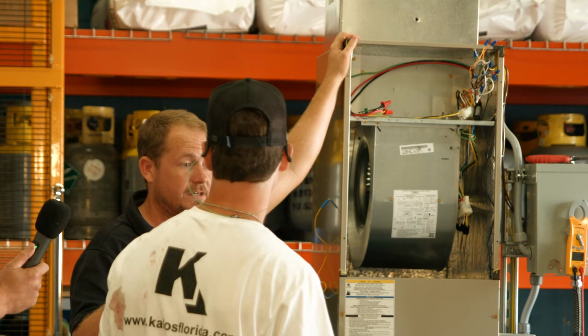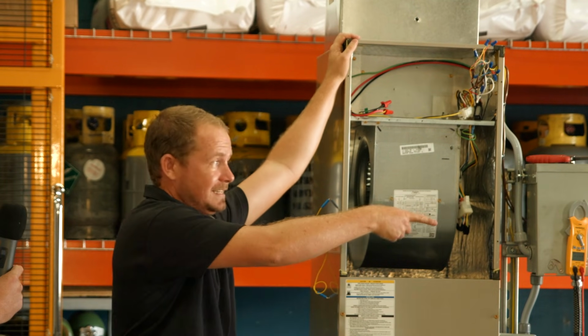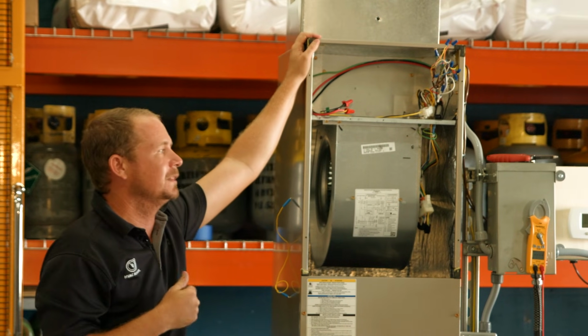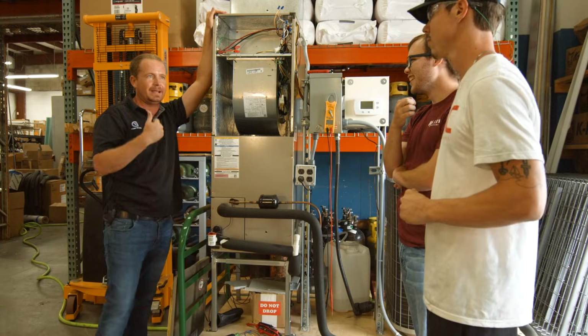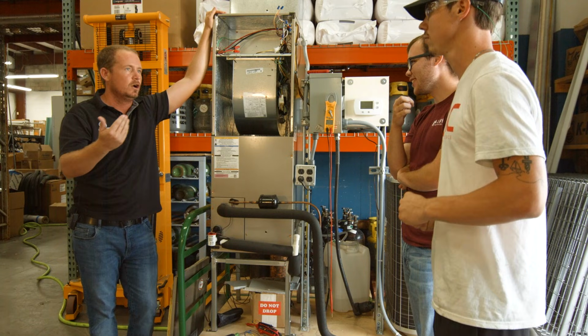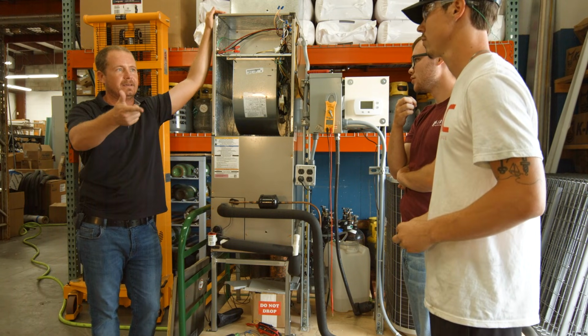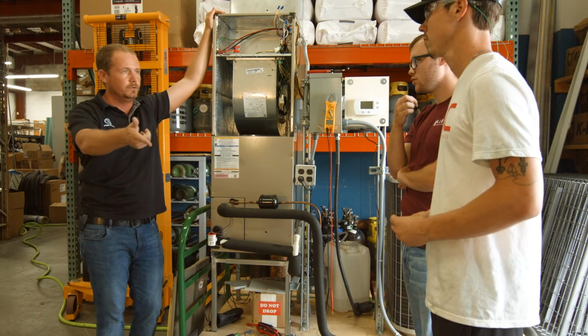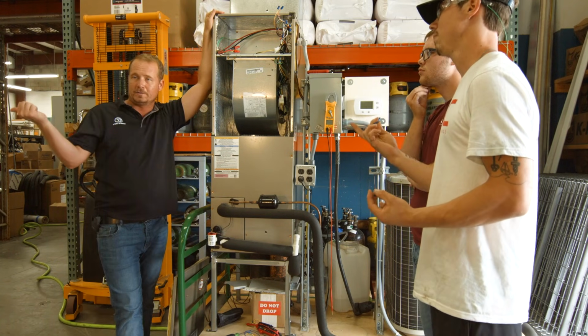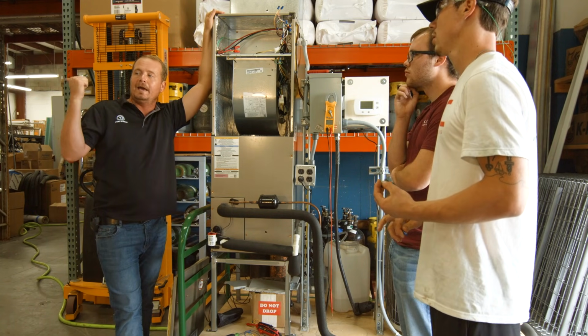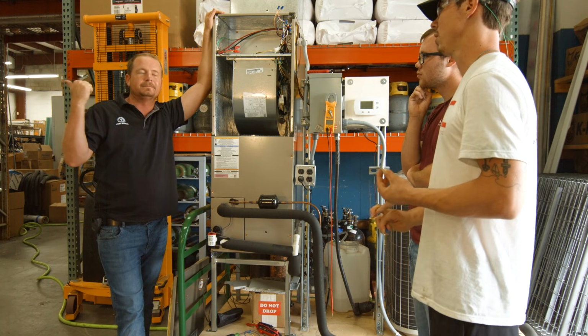Yeah, and that's a good point. And also look if somebody recently replaced the thermostat. Does it look new? That's an indication, because that happens all the time. What's a common mistake that customers make that results in a blown fuse when they wire up a thermostat? They don't shut the power off. That's a common one. And the other is that they'll mishandle the equipment with the reversing valve.